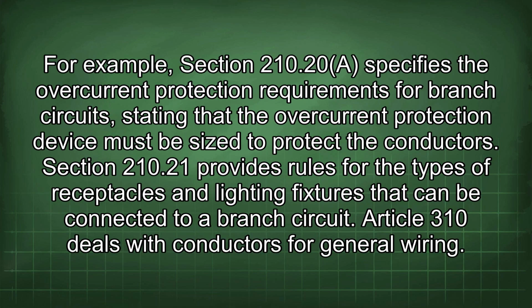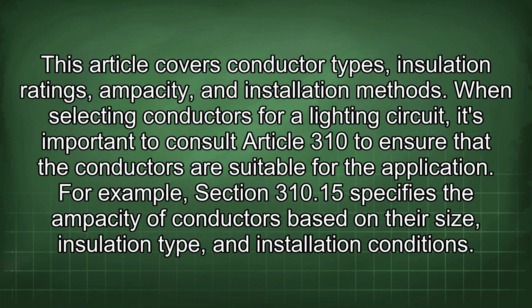For example, Section 210.20 specifies the overcurrent protection requirements for branch circuits, stating that the overcurrent protection device must be sized to protect the conductors. Section 210.21 provides rules for the types of receptacles and lighting fixtures that can be connected to a branch circuit. Article 310 deals with conductors for general wiring. This article covers conductor types, insulation ratings, ampacity, and installation methods. When selecting conductors for a lighting circuit, it's important to consult Article 310 to ensure that the conductors are suitable for the application. For example, Section 310.15 specifies the ampacity of conductors based on their size, insulation type, and installation conditions.